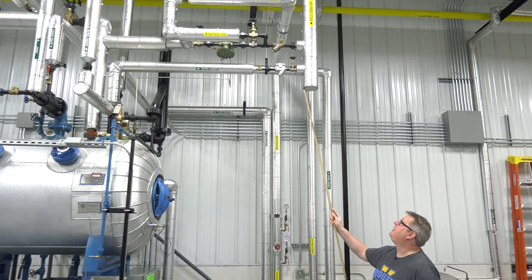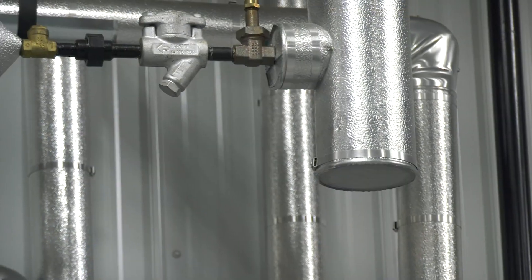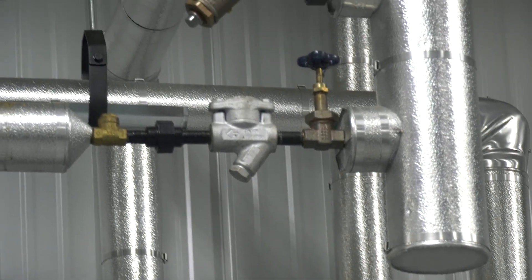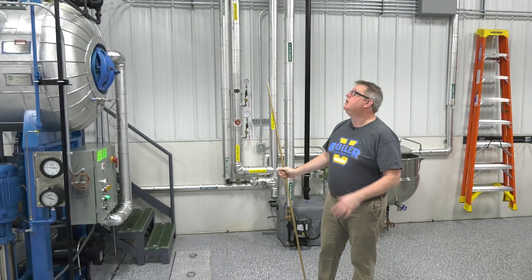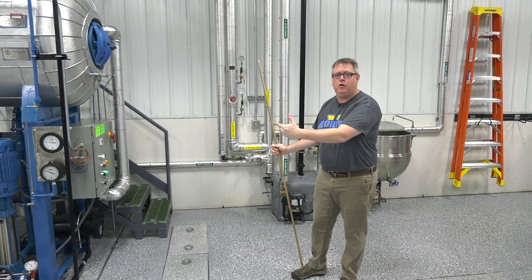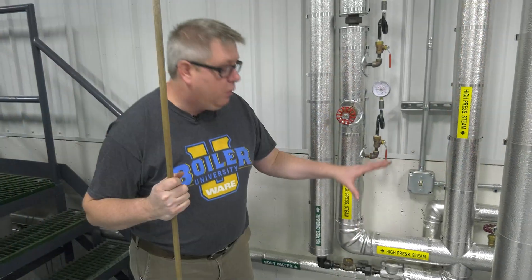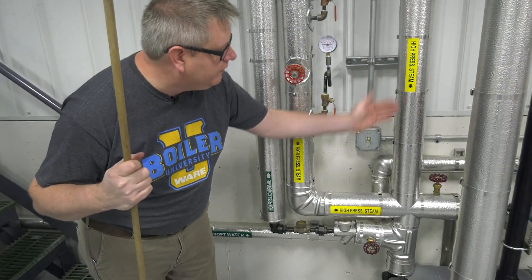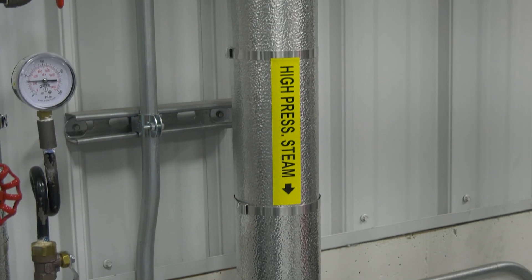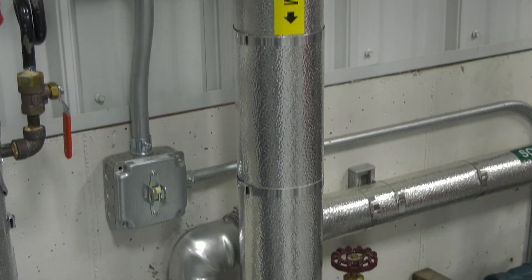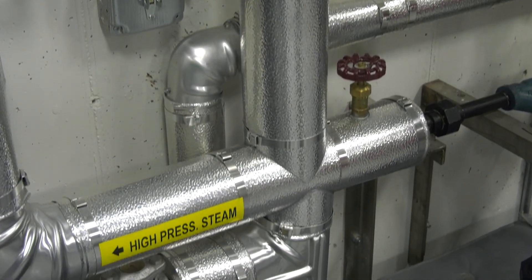We also want to have a trap, a drip leg and trap at any point where we're bringing off steam into a control valve or pressure reducing valve so that we don't get condensate going into that valve. We've got a drip leg here because we've got a drop for our process, another control valve, and we want to keep those lines clear of condensate.